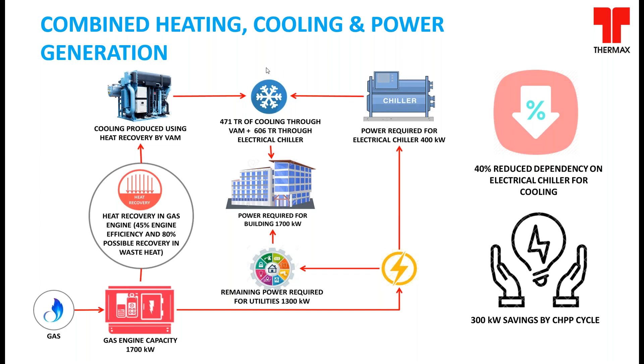Now this is what a typical CHP system consists of. You have a gas engine, and as mentioned, there is exhaust gas coming out of it, as well as jacket water from the jacket water circuit. These two are fed into an absorption chiller. If the engine is off or under maintenance, we can still cater to the cooling requirement by directly firing natural gas inside the chiller. So this equipment can be designed as a chiller or a chiller-heater, delivering cooling in summer and heating in winter. It's purely up to the user's requirement, and we can customize it for different solutions.